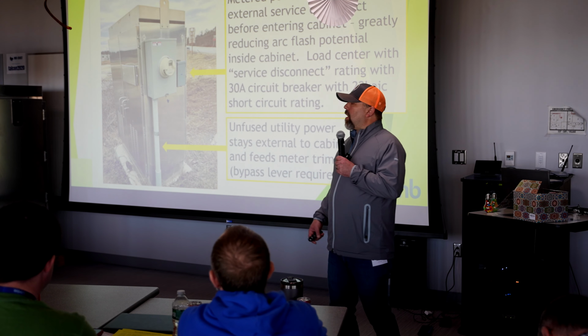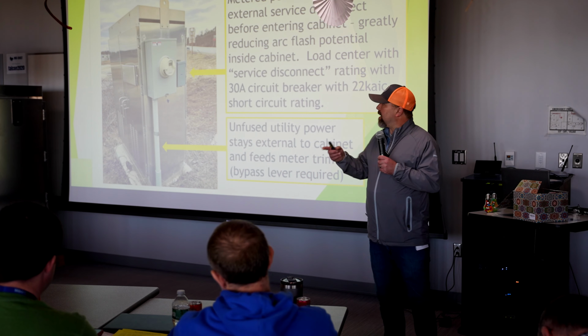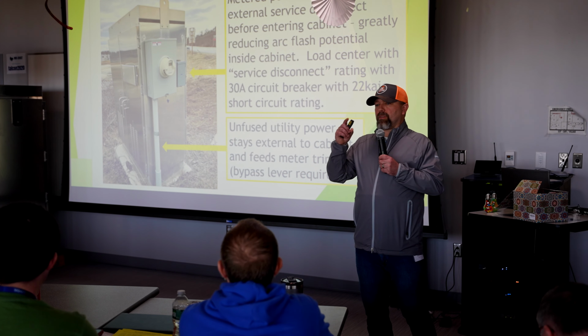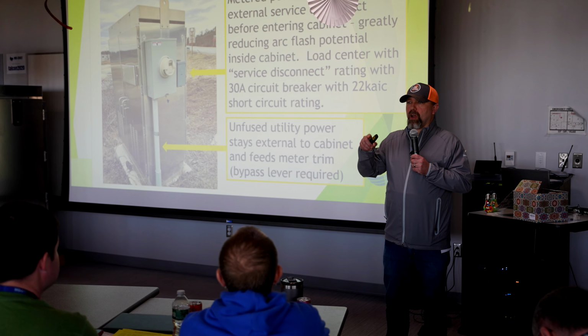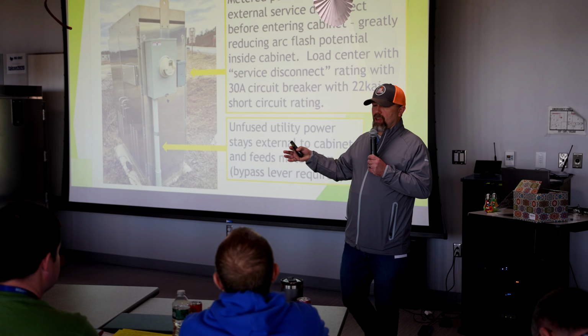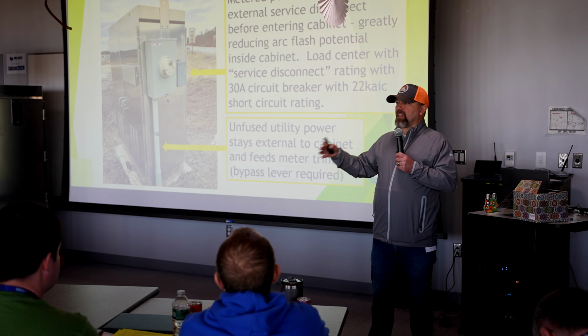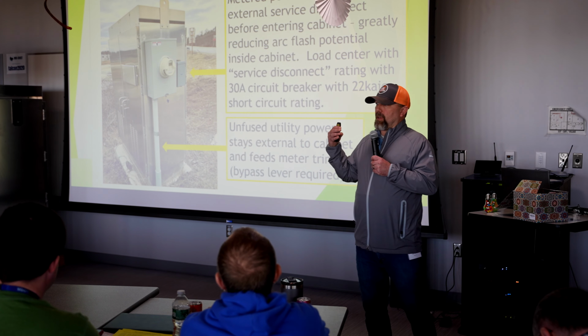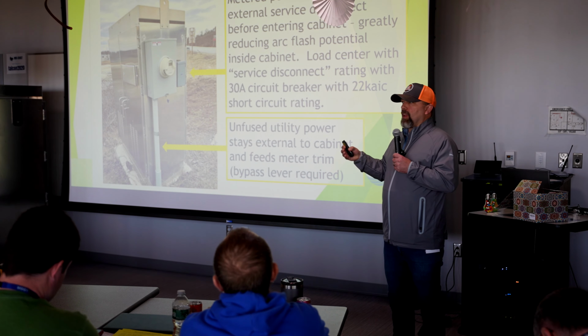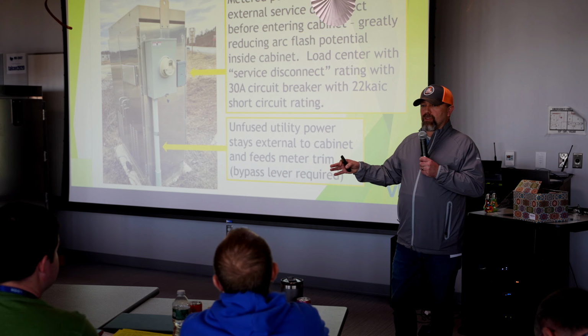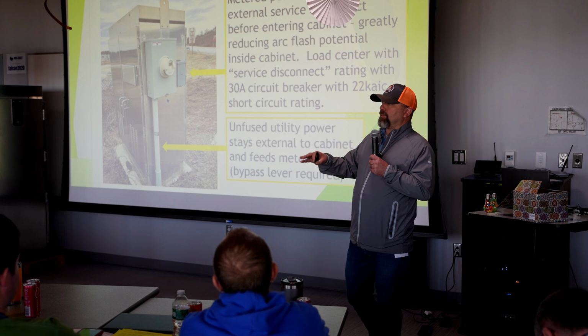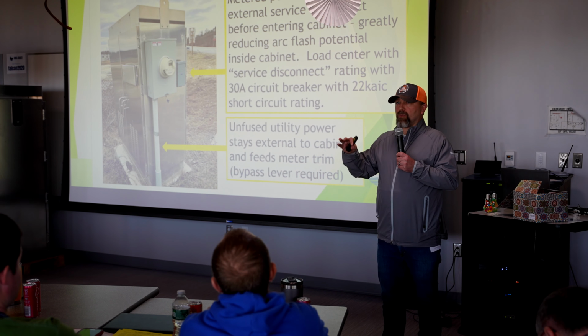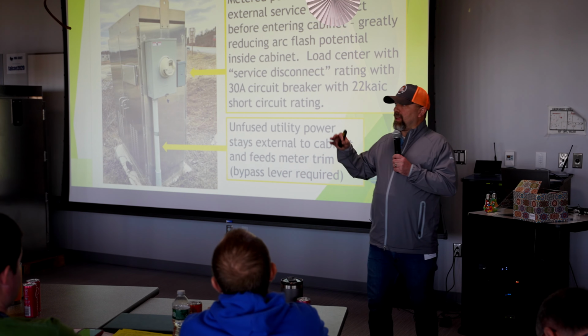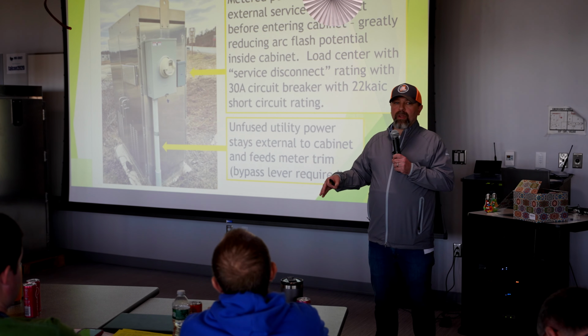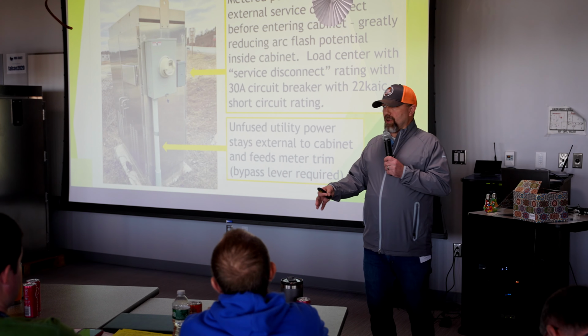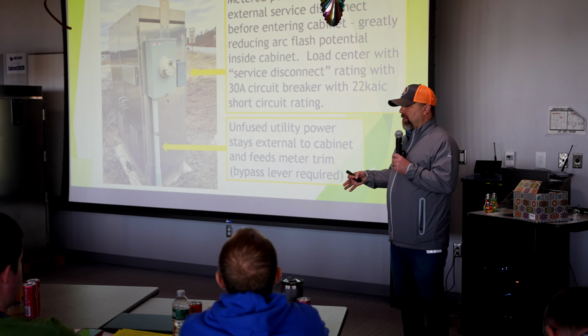One last thing I'd like to bring up, and I know I'm over my time. Yesterday Ron was talking about conduits and when, by DOT policy, conduit has to be steel or concrete encased PVC. When I was on the contractor side, we dealt with this quite a bit, and for a long time there was kind of an unwritten rule. There's always been a rule on the books that any electrical services in Maine DOT right-of-ways are supposed to adhere to that, either rigid steel or PVC encased in concrete.